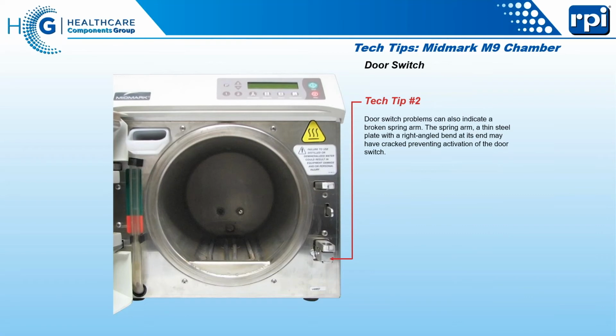Okay, there is a door switch. There is a little bit of an assembly in this door switch that has a very unusual metal bracket. And on the end of that metal bracket is a tiny, tiny lip. They basically bent it into the bracket. It's about, I think, 1/16 of an inch thick. It's really delicate. It can be broken. If you go to do the door switch, just take a look at that just to be sure it hasn't failed as well. Sometimes it'll do that, and it's really tough to find.